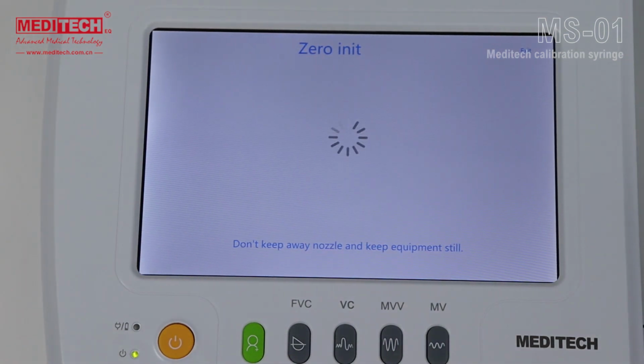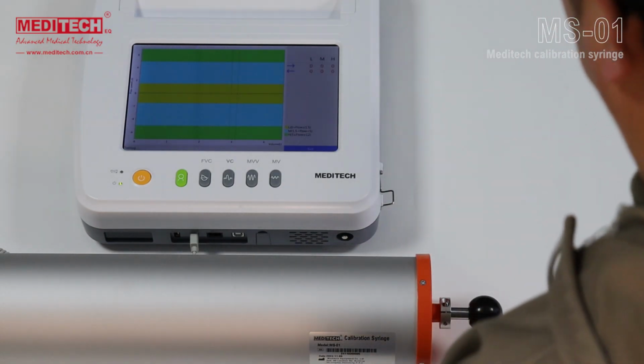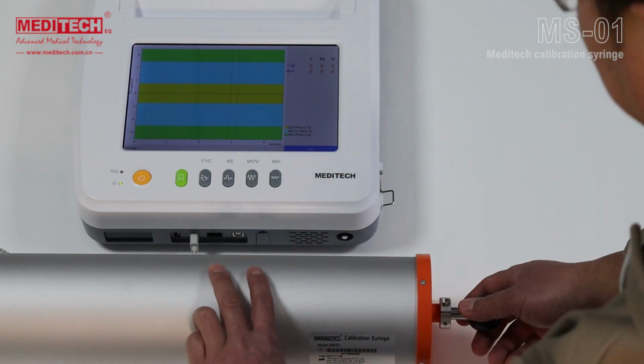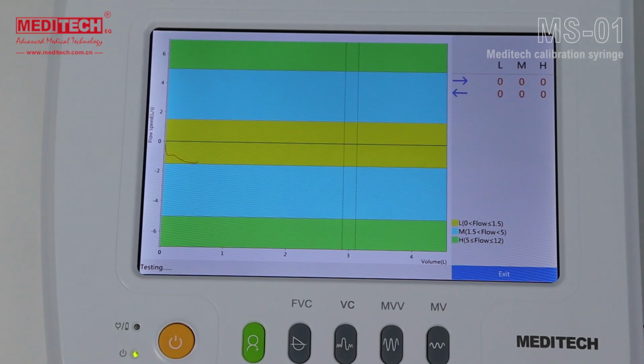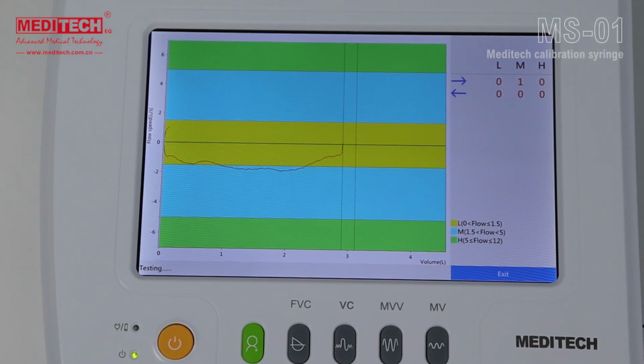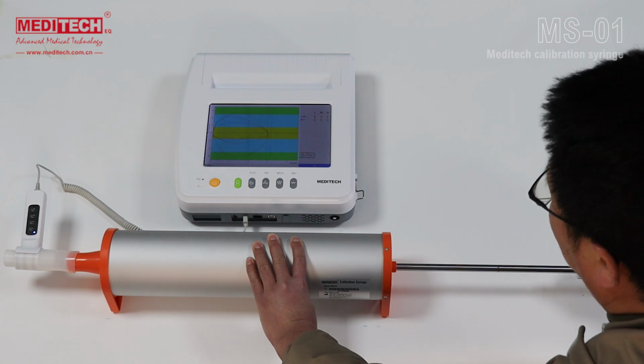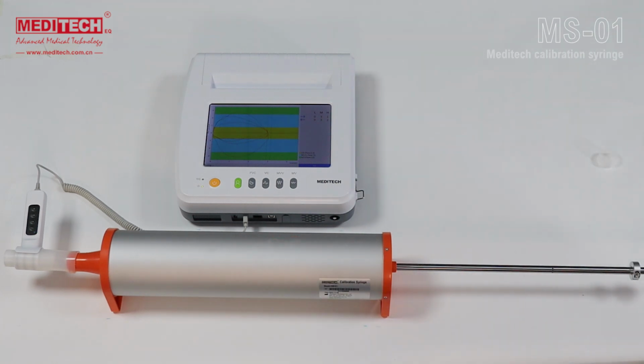Since this spirometer has an automatic zero initialization function, the subtitle Zero Initialization will appear. When the subtitle Zero Initialization disappears, you can perform the push-pull process at 3 different speeds. The first is slow, the second is medium fast, and the last is fast. Once the test is complete, pull the handle to the maximum position.